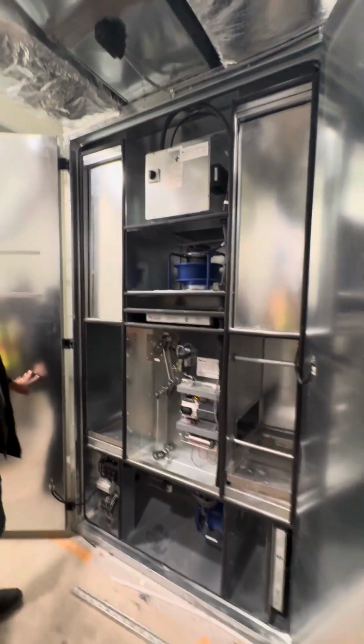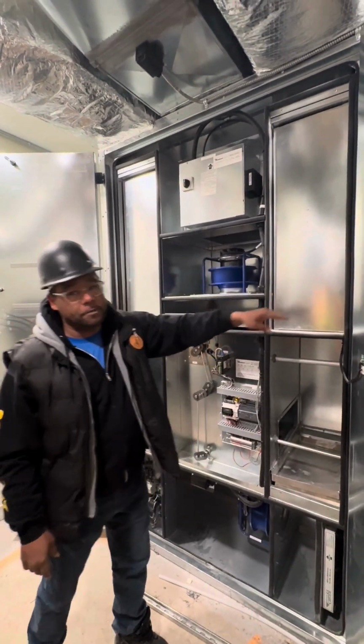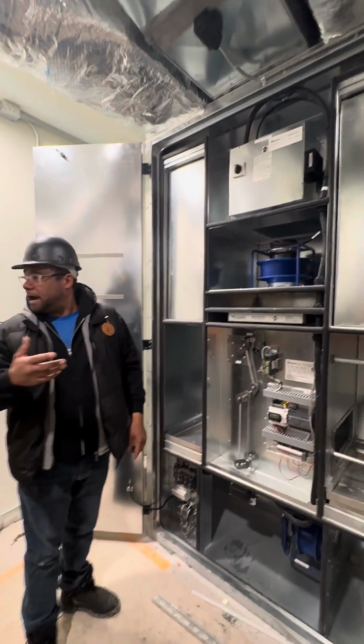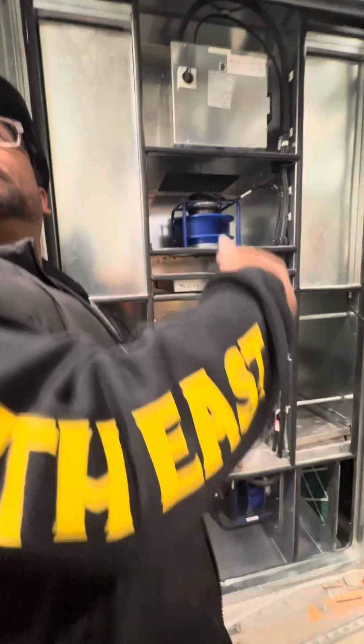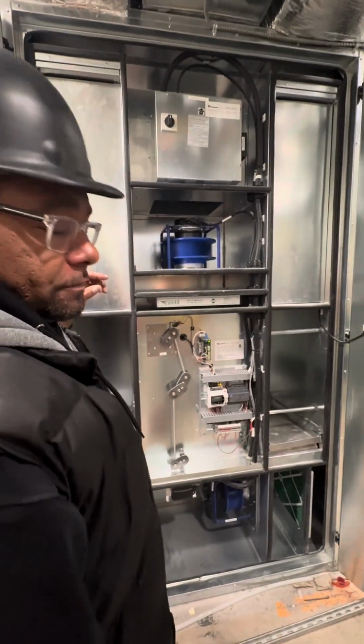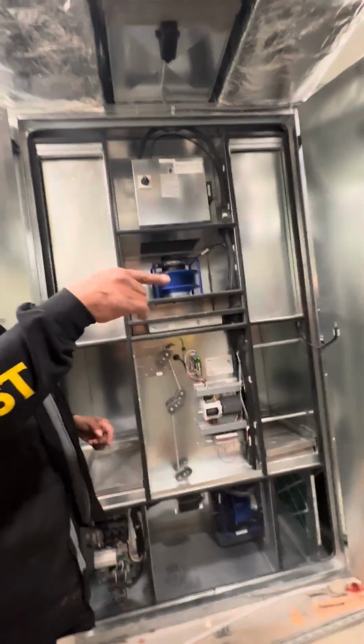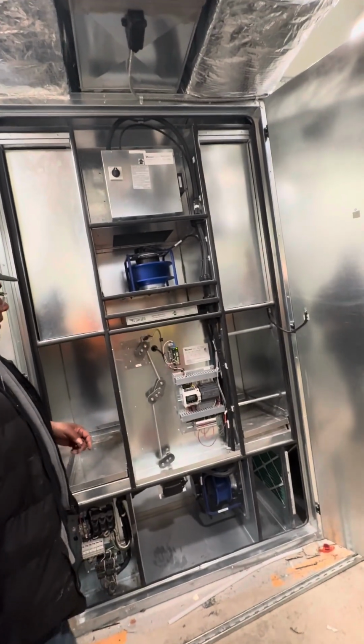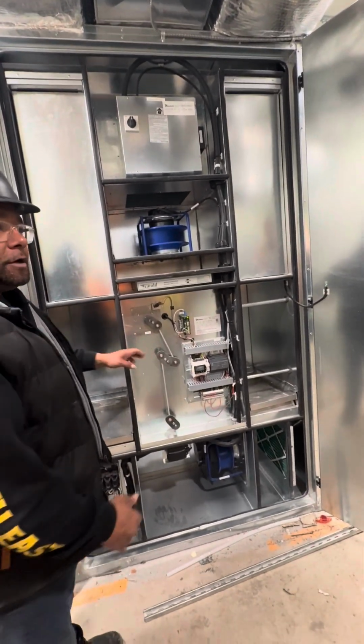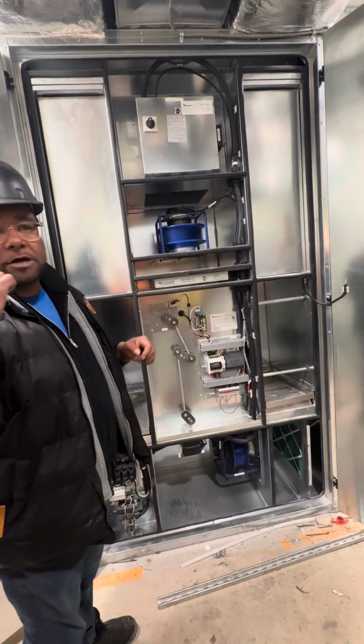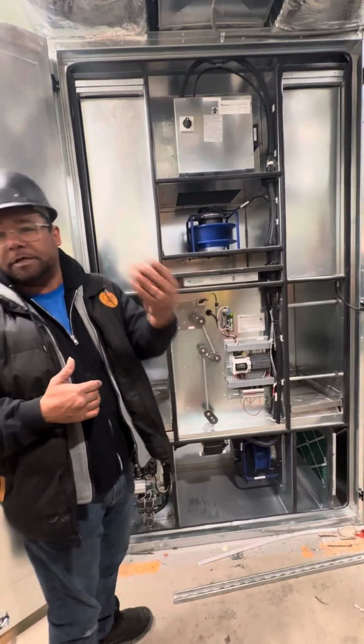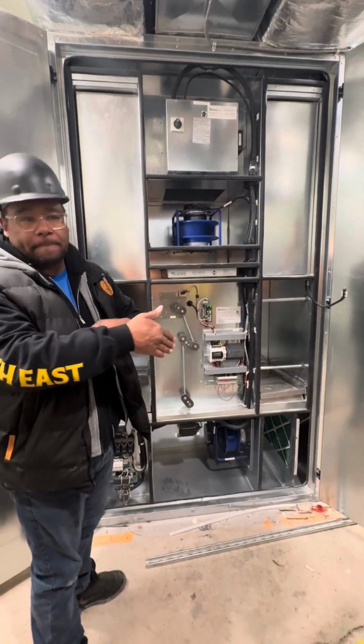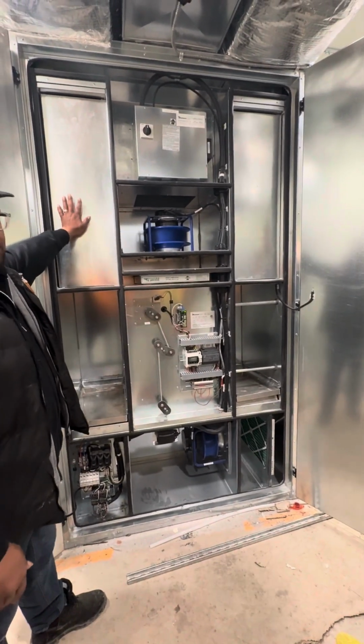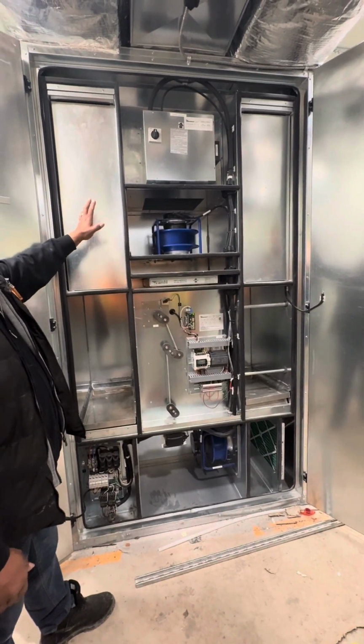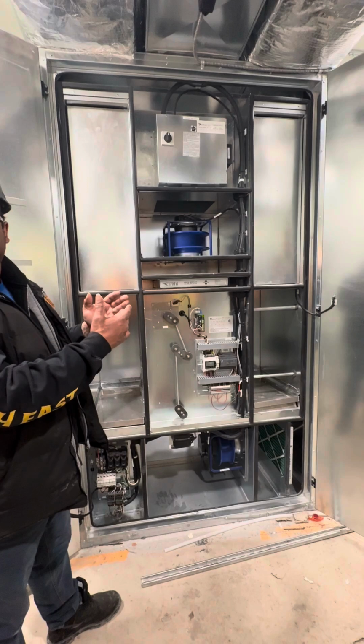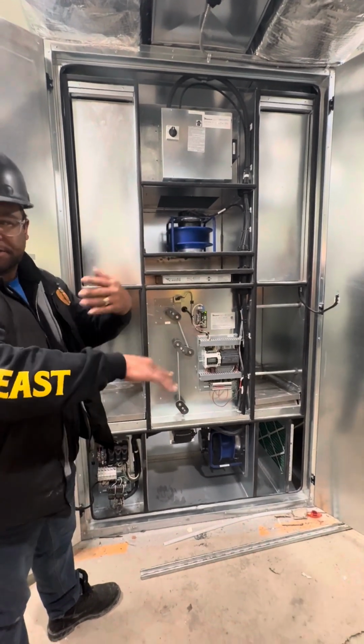Go in here, we have heat exchanger cores. One set is responsible for bringing the exhaust air from the building, the bathrooms and common areas, running it through the cores, and then dumping it outside. The other set of cores runs fresh air back from outside into each suite, including the common areas and bedrooms. They rotate back and forth and change the direction of air, so the exhaust is not always the exhaust and the intake is not always the intake. It'll exhaust for a while, then flip and go back to intake, going back and forth, picking up the heat off these cores. The exhaust goes through the cores, picks up that heat, the fresh air crosses across them, picks up that heat, blows in the air, and then reverses the other way.